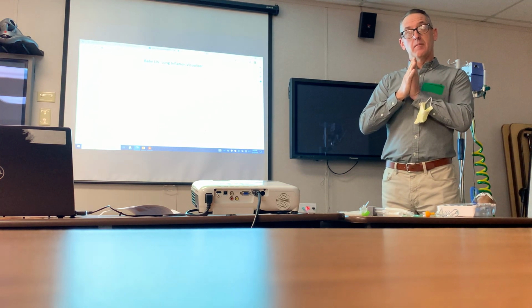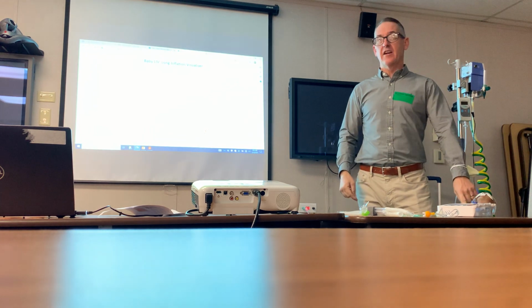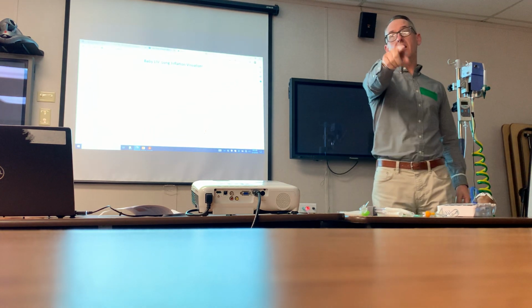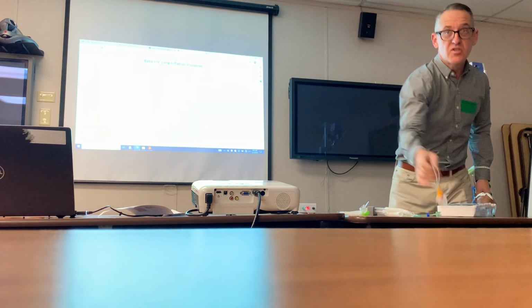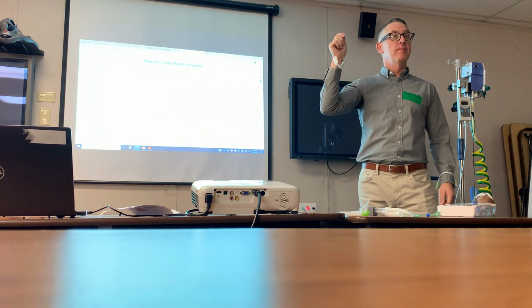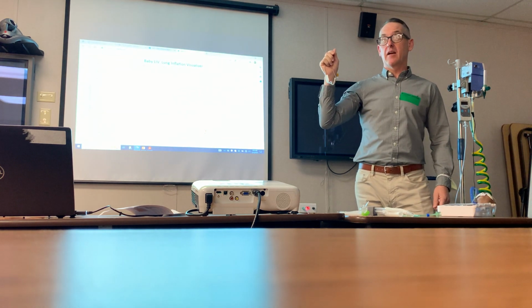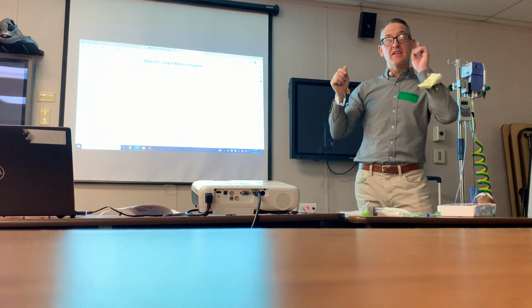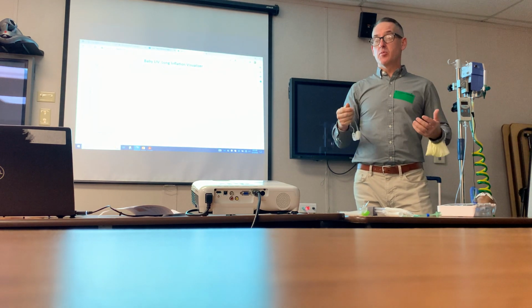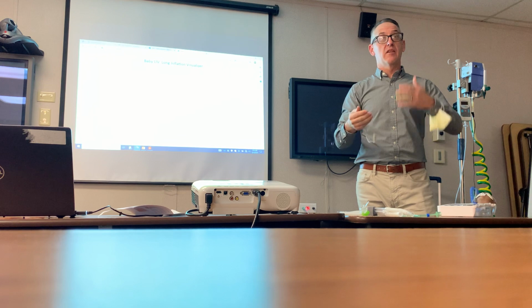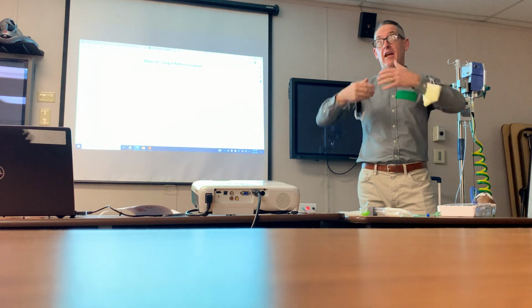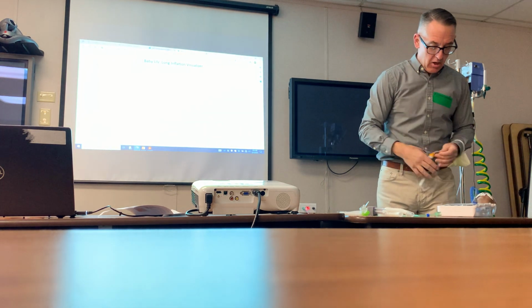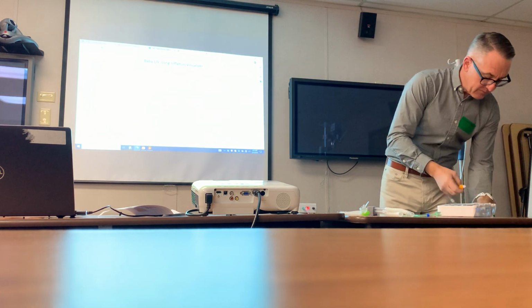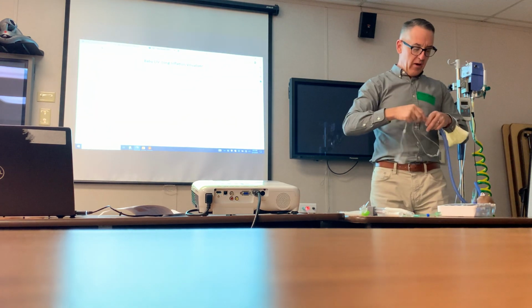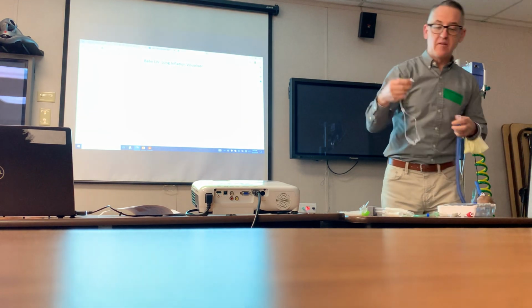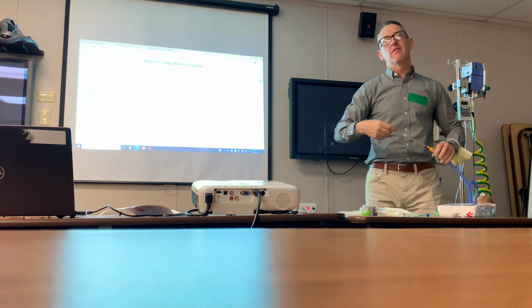Okay, so I thought that with the red cannula, in order to demonstrate that cannulas are safe, it can't be subjective. Meaning, if I chose the red cannula and thought that was 50%, and Tara here thought that 50% was the next size up, does that have a big impact on what I'm doing with the kids? We need to demonstrate that it's safe between the two, because it shouldn't be so subjective that two different people do something and it has a large impact on the therapy. So let's stop this data. I'm going to go from a red cannula that was about 50% to a yellow cannula that's about 60%.